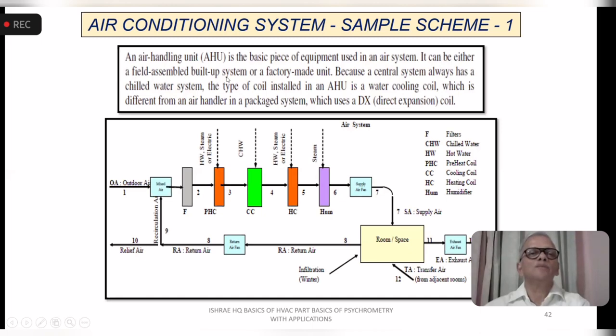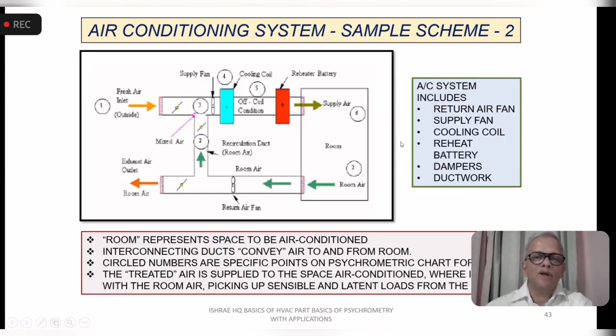It can be either field assembled or factory made. Because the central system always has a chilled water system, the type of coil is a chilled water cooling coil. The idea of this is just to get a hang of a system, with a similar arrangement here. What we are talking about is pumping the air in, which we call supply air. The room represents the space to be air conditioned, which is here. Interconnecting ducts are conveying the air to and from the space to be conditioned.